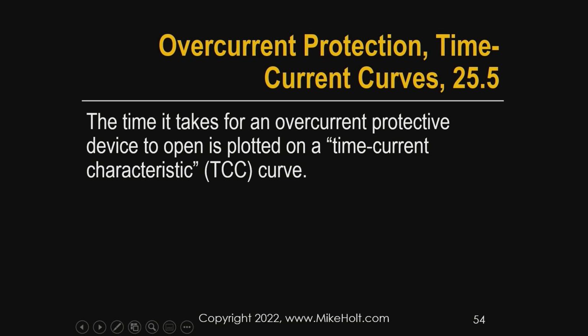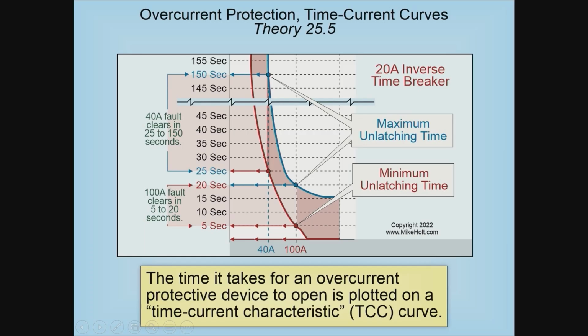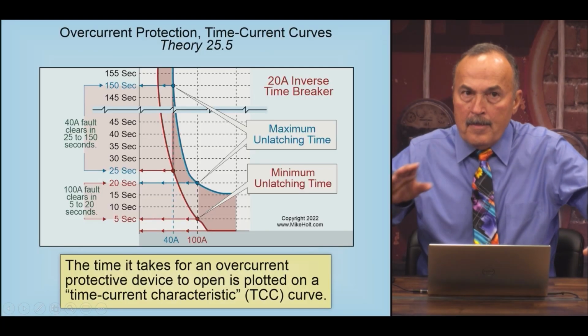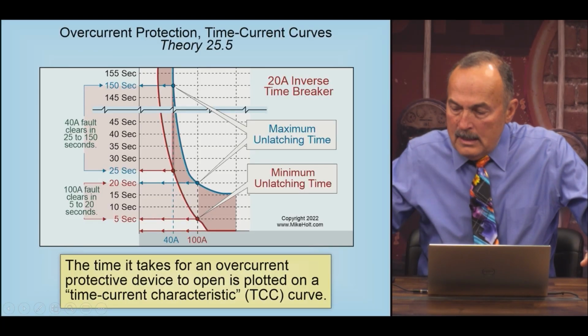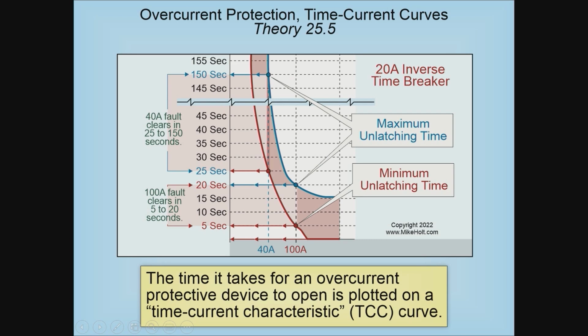Okay, the time it takes for an overcurrent protective device to open is plotted on what is called the time current characteristic curve. It's a pretty fancy name, so let me just explain what it is, and then we can get into some details. Maybe we could put like 1,000 amps over here. So this line right here is amps, the current, on the left-hand side. And then up here is time. You can see it starts at 5 seconds, and of course some values would be significantly less than 5. We're talking about a big broad stroke here.